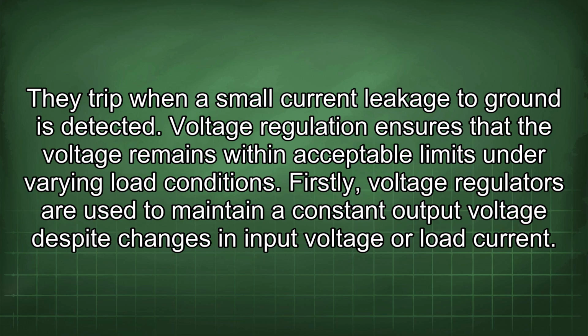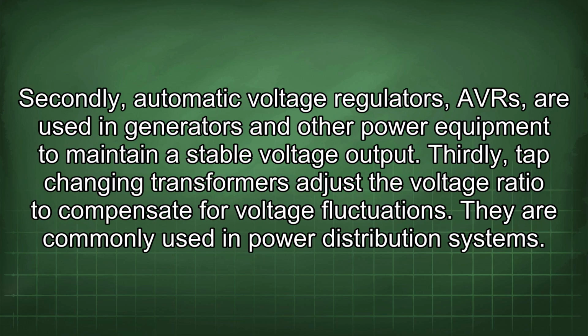Voltage regulation ensures that the voltage remains within acceptable limits under varying load conditions. Firstly, voltage regulators are used to maintain a constant output voltage despite changes in input voltage or load current. Secondly, automatic voltage regulators, AVRs, are used in generators and other power equipment to maintain a stable voltage output. Thirdly, tap-changing transformers adjust the voltage ratio to compensate for voltage fluctuations. They are commonly used in power distribution systems.